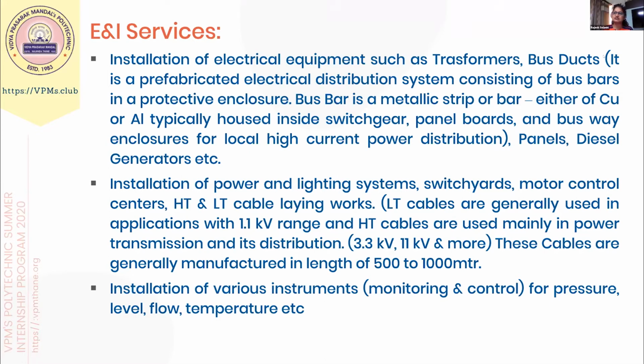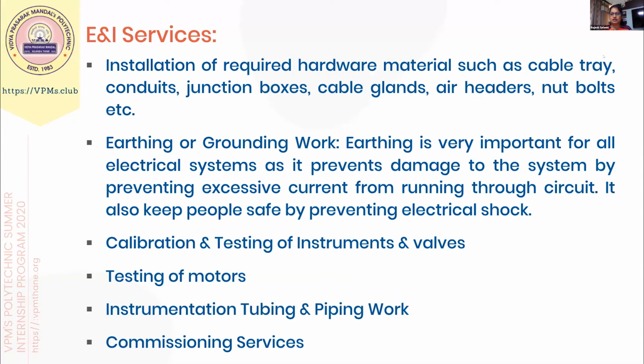Then the next activity is installation of various instruments. Instruments like monitoring instruments and control instruments for various parameters are used depending on the application at the project site, which can be pressure, level, flow, temperature, etc. And the next activity involves the hardware installation. Hardware installation is an important part of E&I construction, which includes cable trays. We'll study about it a little. Conduits, junction boxes, air headers, and small nuts and bolts too.